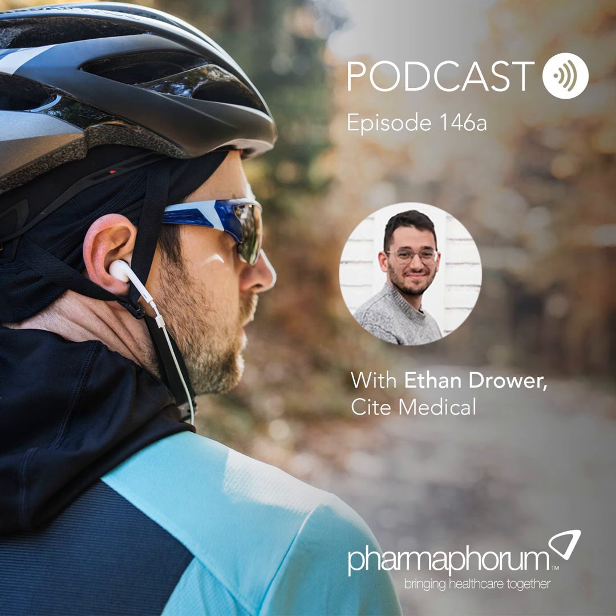So all the data, anything related to your device that can be useful, we need to address it. You cannot selectively choose data. If it exists, it needs to be reported effectively in this section. The third section is going to be your appraisal. So great, we've taken this block of massive data. Now we need to actually determine what of it is acceptable and relevant, and how relevant it is. Certain data is weighted as more valuable, right? If you run a very specific study about your product testing this exact thing, that's far more valuable than a customer survey. But all data needs to be accounted for and appraised in that section.